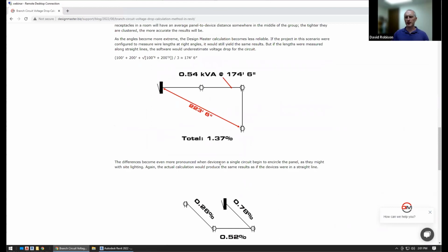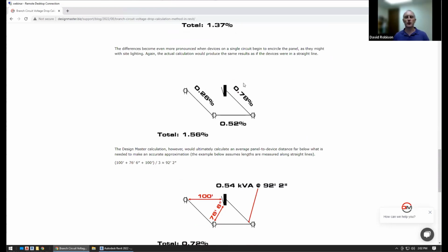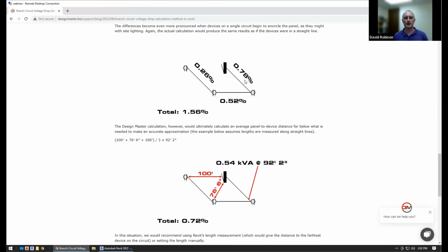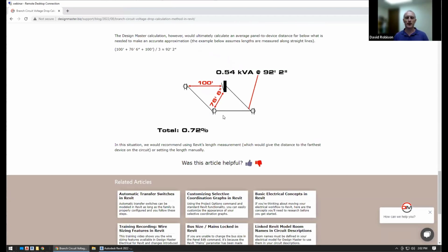These devices are spread apart, fairly distant. They're 100 feet apart. Normally, you end up with a bunch of receptacles all clustered together, so the differences end up being minuscule in most cases. It's only when you have these long runs, so it's really site lighting and things like that, where this might ever come into play. Just as another example, if you have some situation where the devices are kind of circling around the panel, again, we're not going to be as precise in our calculation. Again, same distances, just arranged differently, so the voltage drop isn't the same. The average distance from the panel to the receptacles is 92 feet, so we get a lower voltage drop, 0.72%.